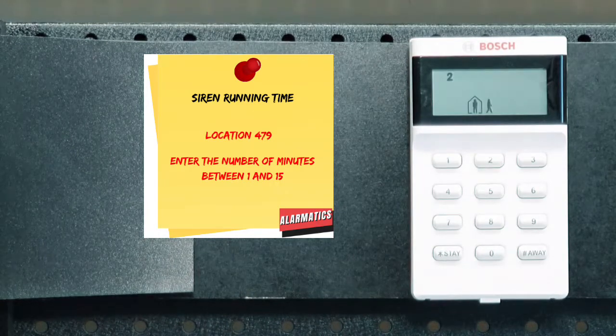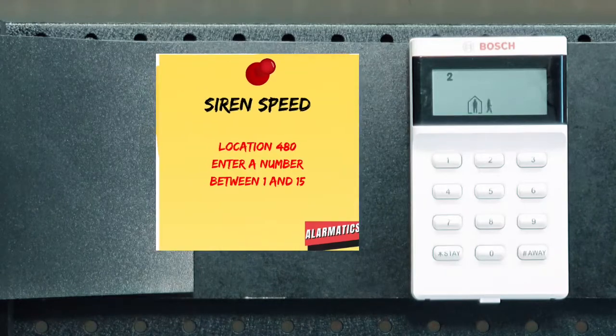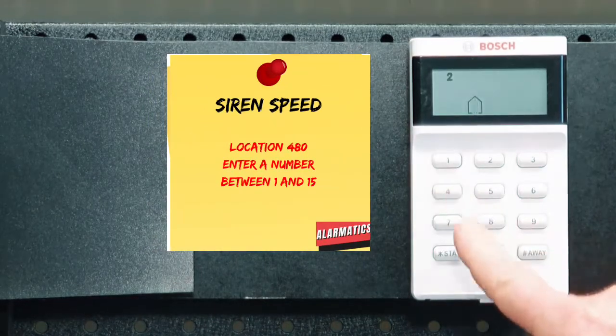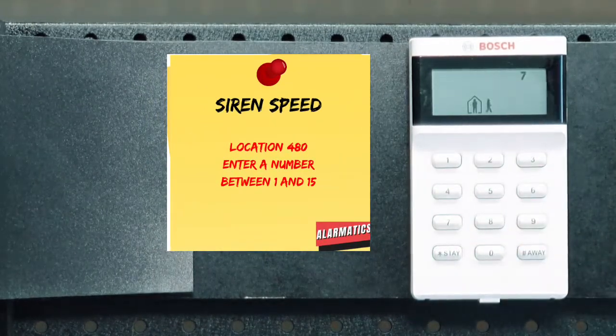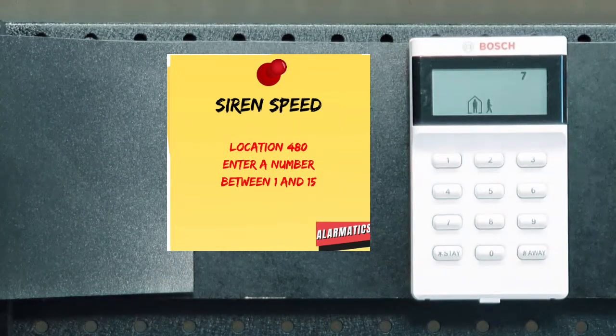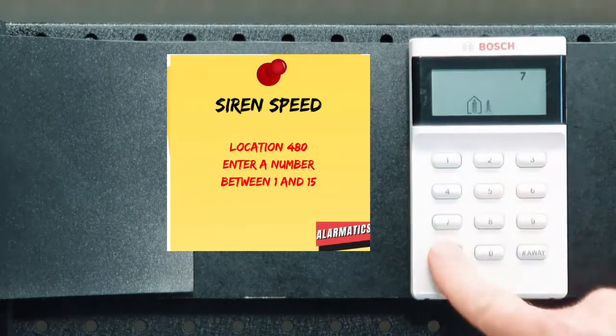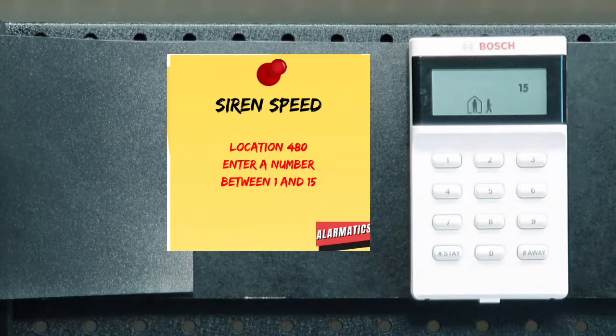The other setting I like to change here is the siren sound rate, which is located at location 480, so I'll jump to 480. This is how fast the siren sounds, the speed of the siren. So 0 is a really slow, ooh, ooh, ooh siren. If we turn that up to 15, which is where I like to put it, it's this nice quick siren that gives that sort of sense of urgency. So let's make it 15. Again, play around with that. You can set that for anything you like.